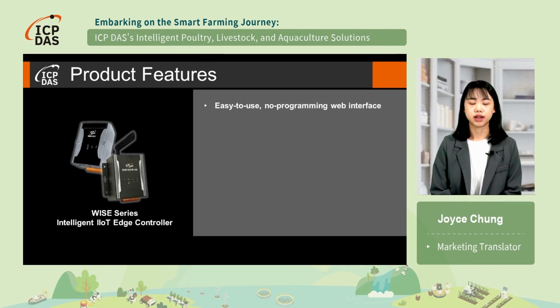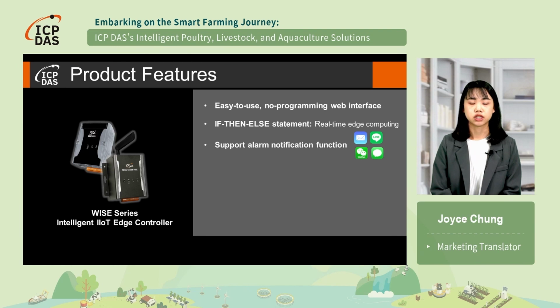ICP-DAS WISE series Intelligent IIoT Edge Controller provides an easy-to-use web interface, making system configuration a breeze and eliminating the need for programming. A standout feature of the WISE series Edge Controller lies in its if-then-else statement capability, enabling the execution of real-time edge computing with efficiency and stability. Suppose an interruption of the communication between the controller and the control center occurs. In such case, the WISE series placed in the field still performs real-time edge computing, calculation, and scheduling, no matter whether it is connected to the control center. And it can send alert messages via email, Line, WeChat, and SMS.